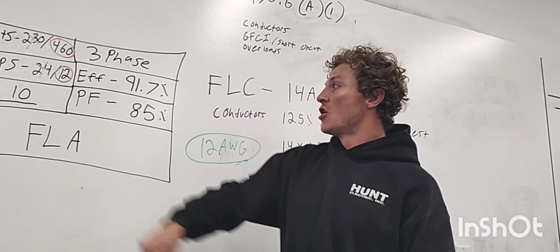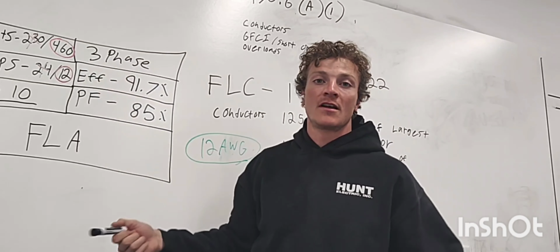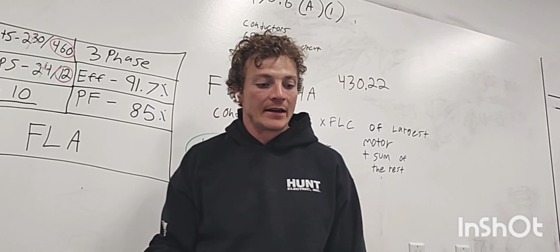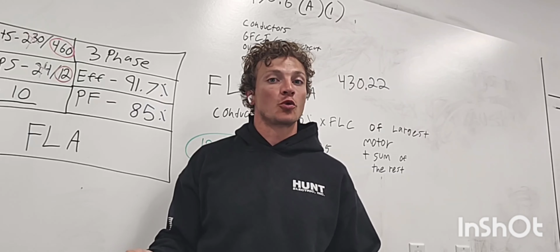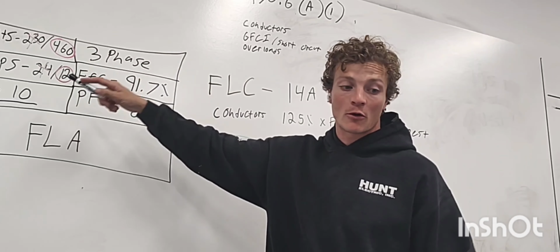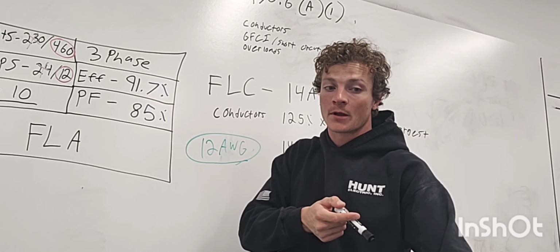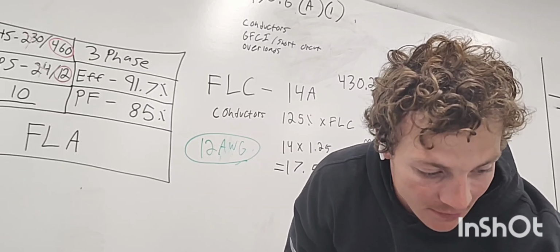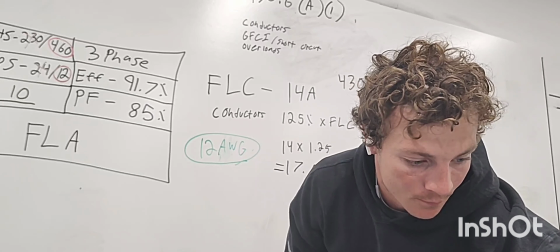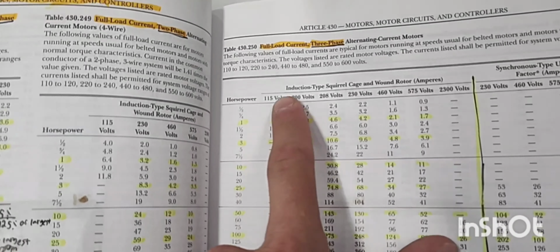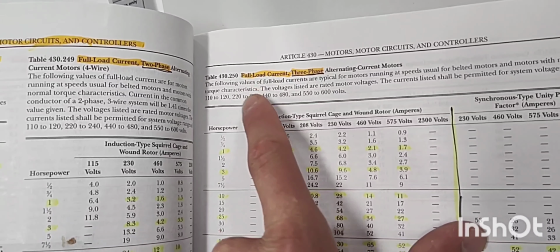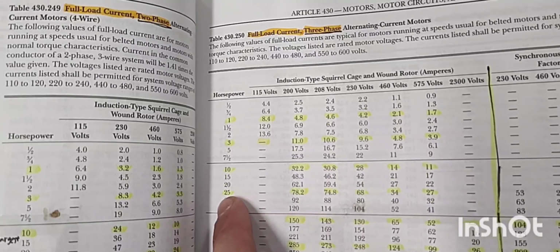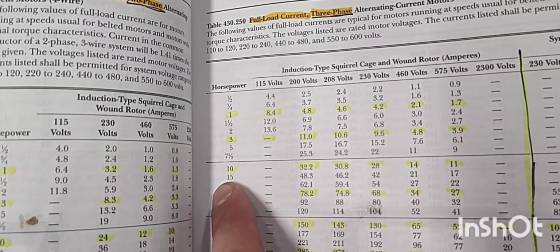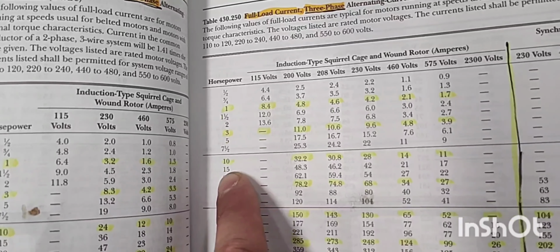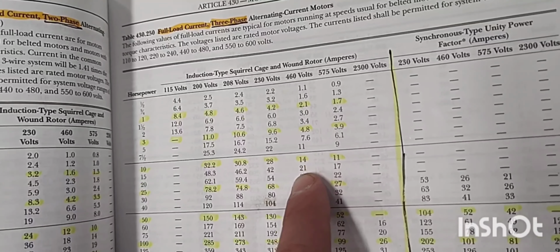We just get our horsepower from there. Say we had one that was 12 horsepower, 460 volts. That one's going to be higher amperage. And we're going to do 125% of the 12 horsepower one off the NEC. So let's go into this. 3-phase, table 430.250, 12 horsepower. Let's say it's 15 horsepower. How about that? 15 horsepower, 460 volts, 21.